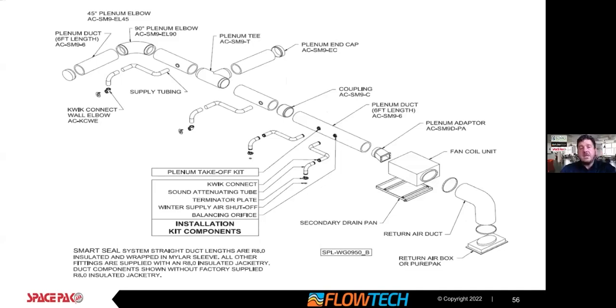So this is the air side distribution for SpacePak. A lot of times we see these in combination with radiant floor heating, as maybe we're cooling the upstairs. So we have a lot of design flexibility with hydronics, which is one of the things that I really love personally. It's exciting to be part of. What we're showing here is our fan coil unit. It has a condensate drain, and it feeds into a 9-inch or equivalent branch ducting. And from that 9-inch branch ducting, we have flexible 2-inch mini ducts that thread throughout the house.